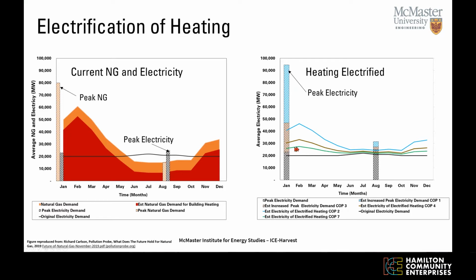So if we used waste heat resources, what would happen? That's a huge challenge in itself, increasing our electricity capacity up to 50,000. But the real challenge is increasing our peak. If you look at the coldest day of the year, how is an air source heat pump going to perform? It's going to have a COP of 1, essentially electrical resistance heating.